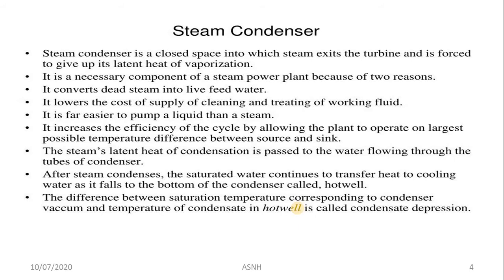So here you will get an idea about the theory related to the steam condenser. The steam condenser is a closed vessel into which the steam exits the turbine and is forced to give up its latent heat of vaporization. In the condenser, the latent heat of condensation is released and a phase change occurs from vapor to liquid. Further, that liquid is sent to the boiler through the condensate extraction pump as well as from the hot well. So this is all about the steam condenser.